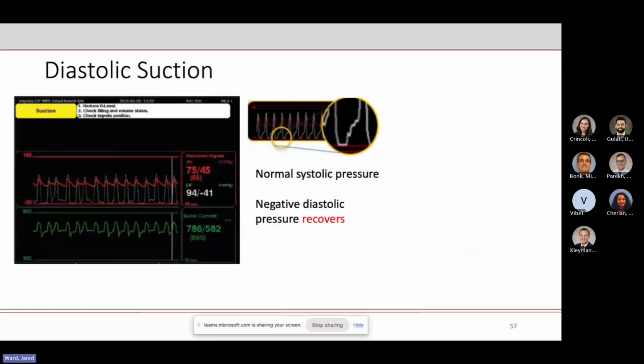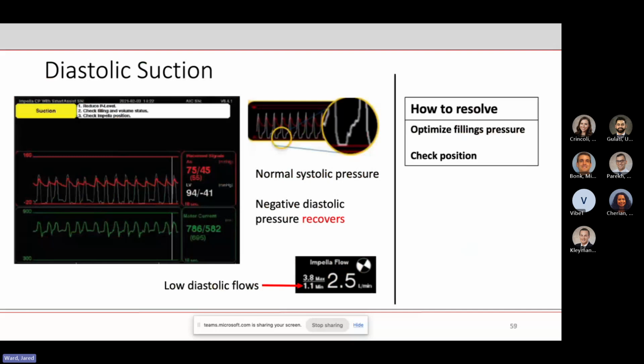So with the Smart Assist, there's two different kinds of suction alarms that occur. There's a diastolic suction alarm. And if you zoom in, you basically see that the LV waveform does recover from the negative pressures. It ends up looking like a normal LV waveform on the left side in the white. Your diastolic flow will be low, meaning the bottom number on there will be low, but the top number, the 3.8 liters, will still be fine. So this is basically optimize your pressures and check the positioning.